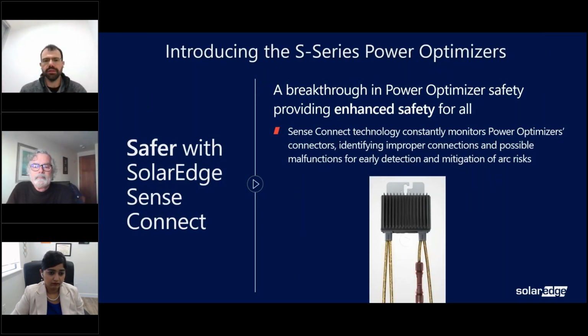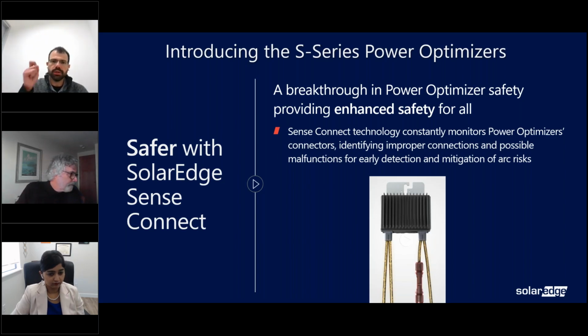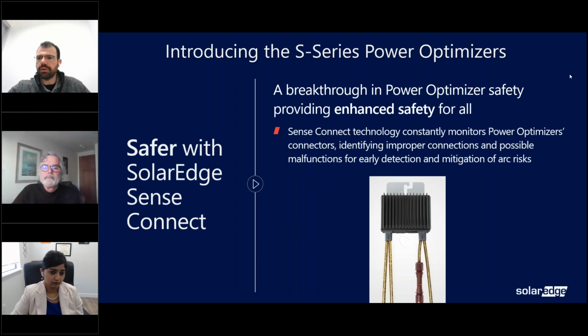Keeping this problem in mind, SolarEdge came up with a patented, innovative solution: we measure the temperature of the connector at the output of this optimizer, where you have higher current going through your string. We check whether there is a problem going on with the connector, and we catch it before things happen. We constantly monitor, and if there is a problem, we bring the system down and disable it, catching it early and preventing catastrophic events.